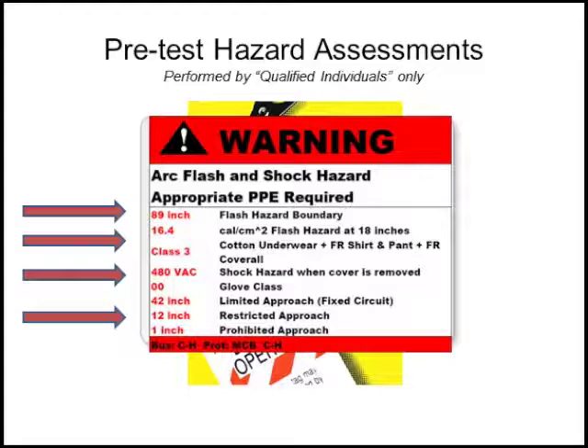You can see on this label here, it indicates our flash protection boundary, in this case 89 inches, the flash incident energy, which is posted here as 16.4 calories, which puts us into Class 3 clothing. Now, I want to point out that the hazard category for the meters is different than the hazard category for clothing. Also on this label, we see the voltage and the proper gloves to wear.